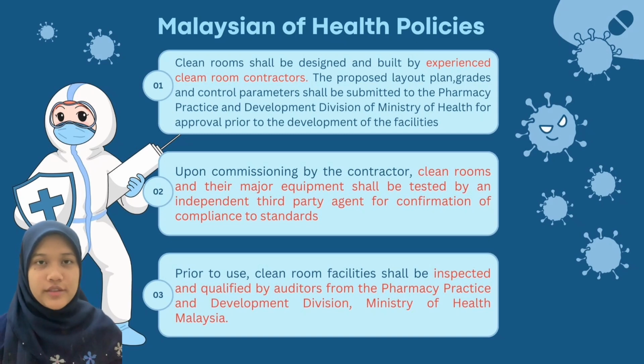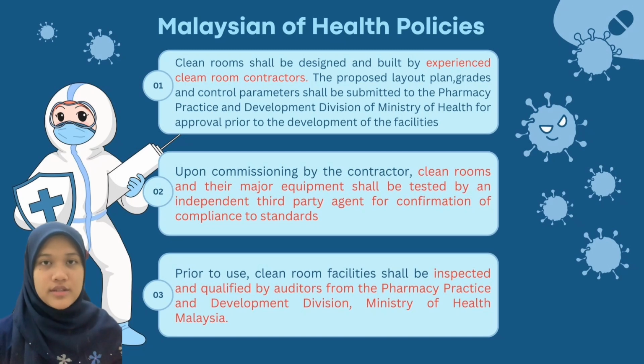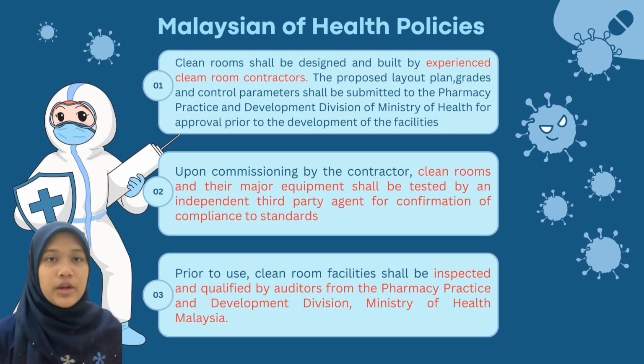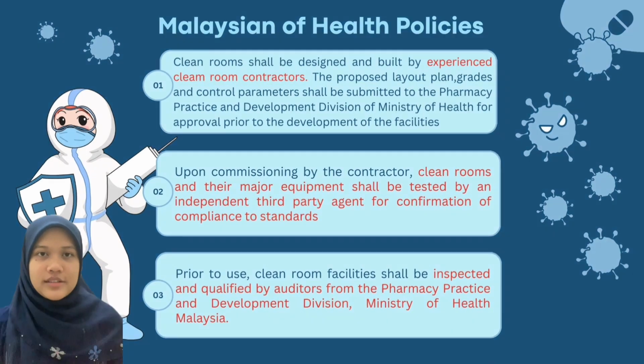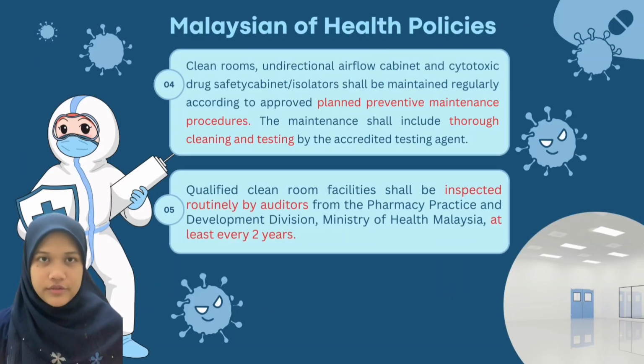Upon commissioning by the contractor, clean rooms and their major equipment, which are laminar airflow cabinet and cytotoxic drug safety cabinet or isolator, shall be tested by an independent third-party agent for confirmation of compliance to standards. The testing agent shall be accredited by appropriate accreditation bodies such as National Association of Testing Authorities, Australia, or National Environmental Balancing Bureau, USA. Prior to use, clean room facilities shall be inspected and qualified by auditors from the Pharmacy Practice and Development Division, Ministry of Health, Malaysia.